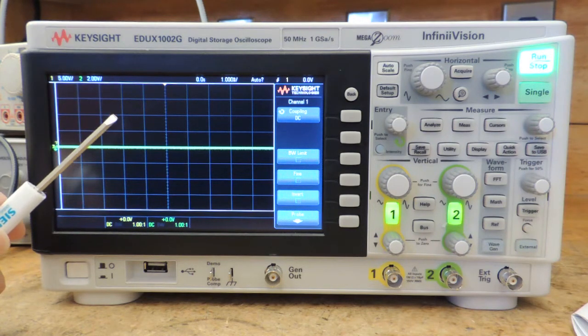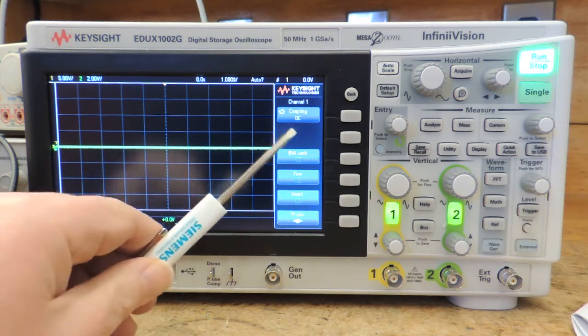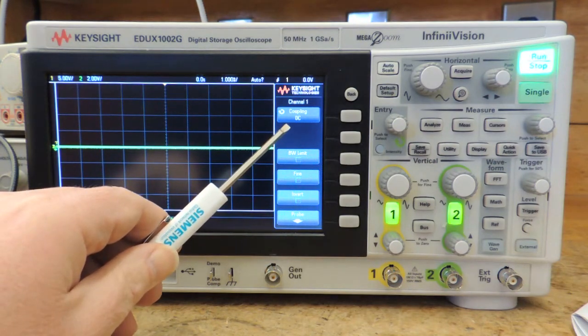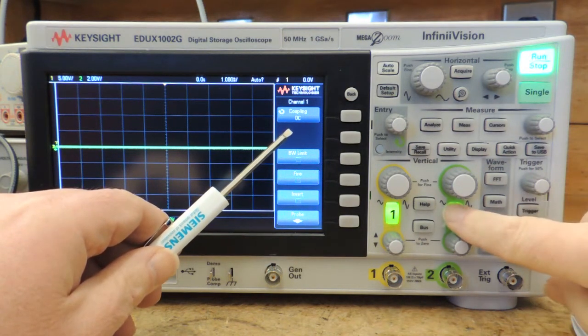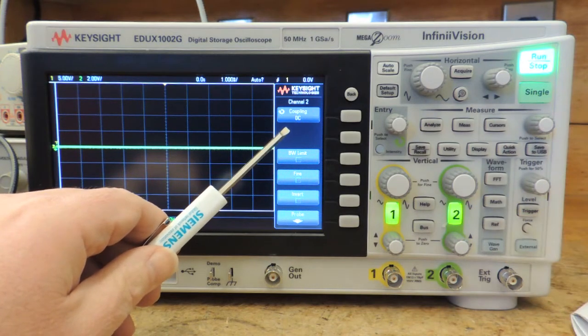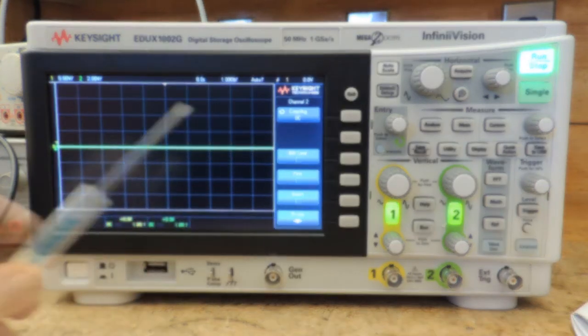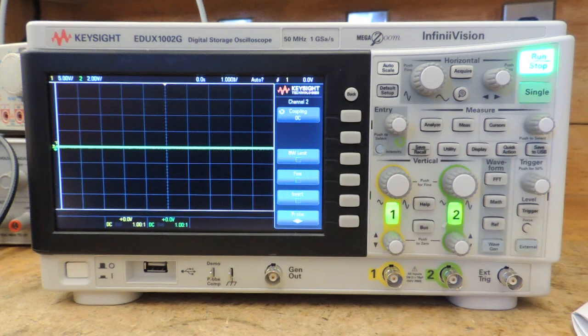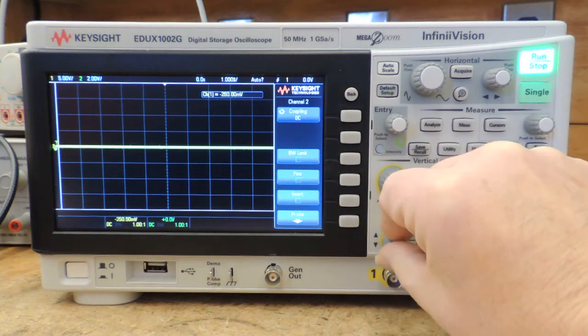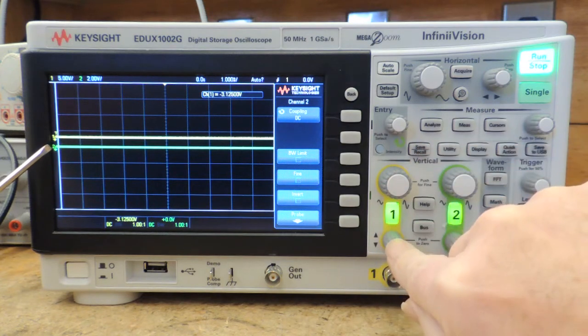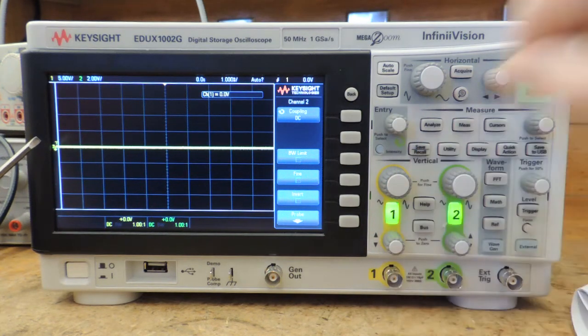It says finally set the input coupling to DC. So channel 1, the coupling is on DC already, and channel 2, the coupling is on DC. And lastly, it says align the display lines to the center line of the display via the positioning knob. Okay, so that was the positioning knob, and if you need to get it to the zero line, you just press it in and it automatically zeros it for you.